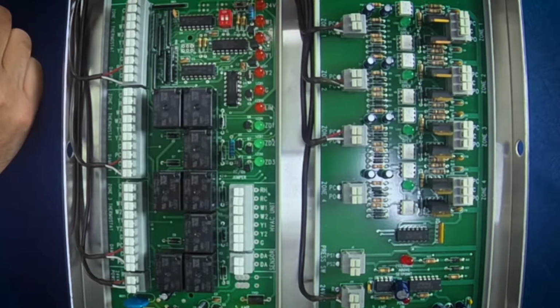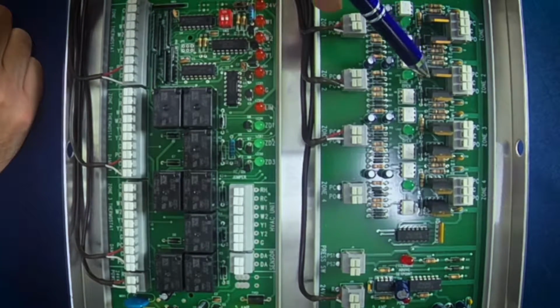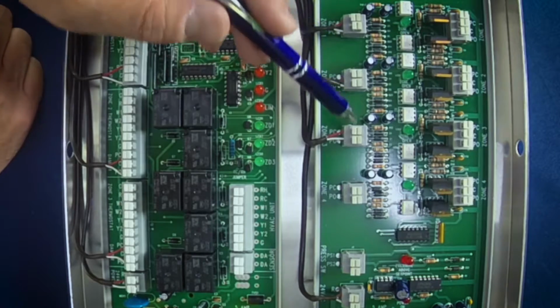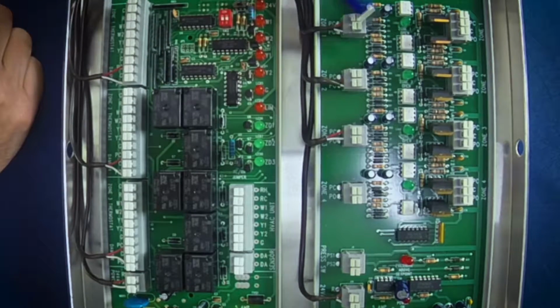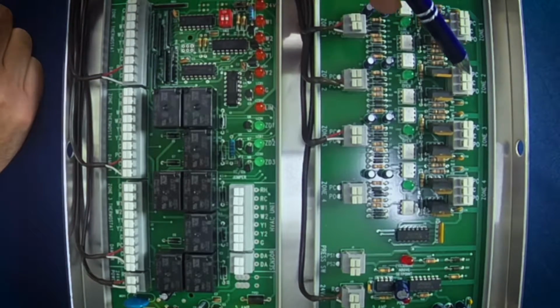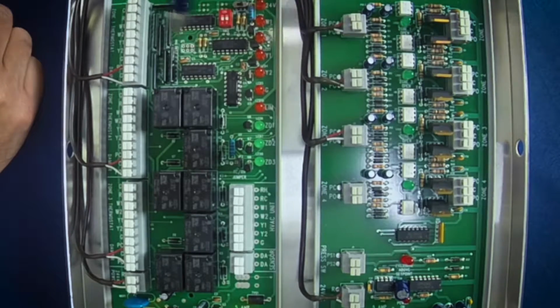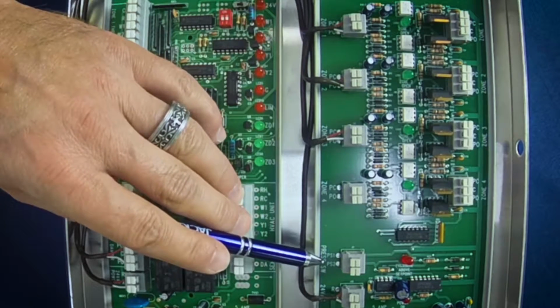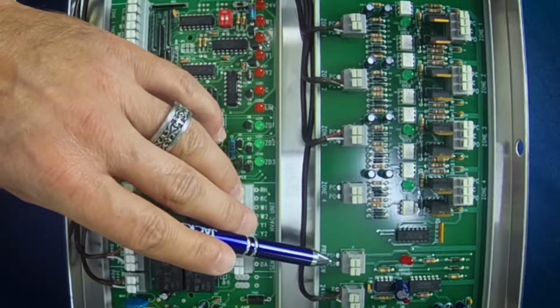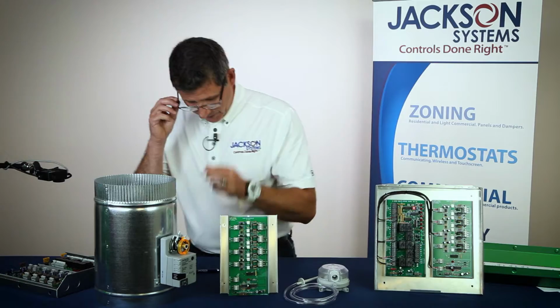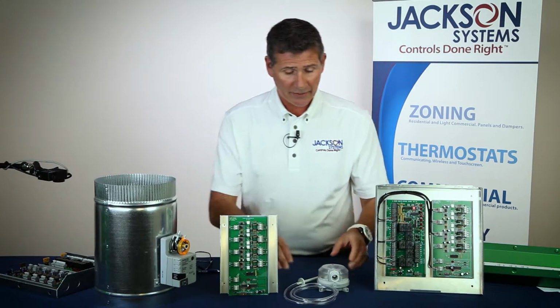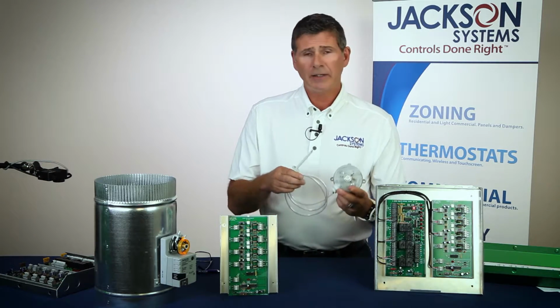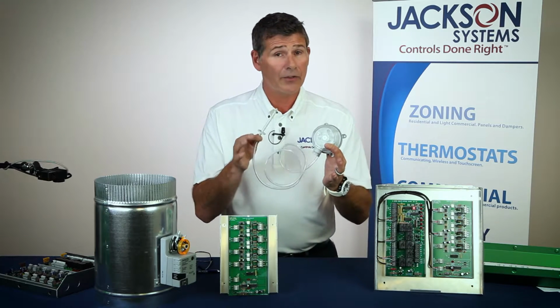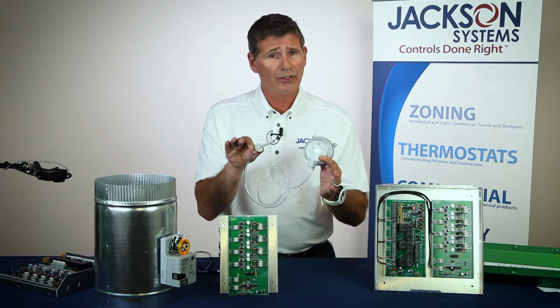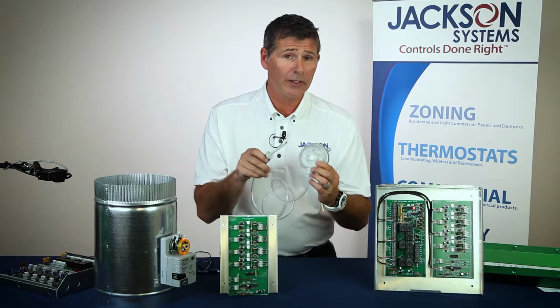Now coming over to the ESP, real quickly before I wrap up, again, these are already wired for you from the factory here. You don't have to worry about that. You're just going to need to wire in your dampers to match up with the thermostats that you've wired in. And then finally, you're going to be wiring in your static pressure control sensor here. And again, this is the module here, the sensor that you're going to be wiring in. And you're going to be putting this approximately 6 feet down inside the ductwork, and this is going to constantly monitor the static pressure in the system.